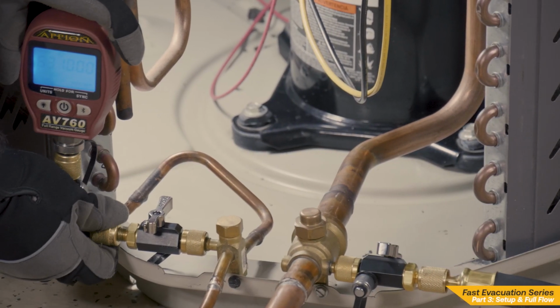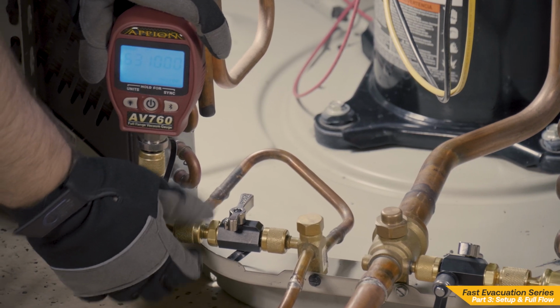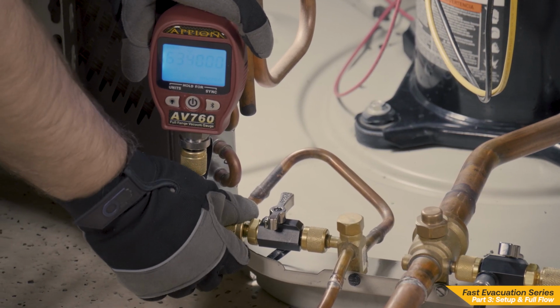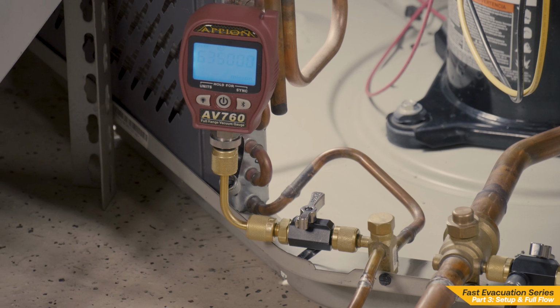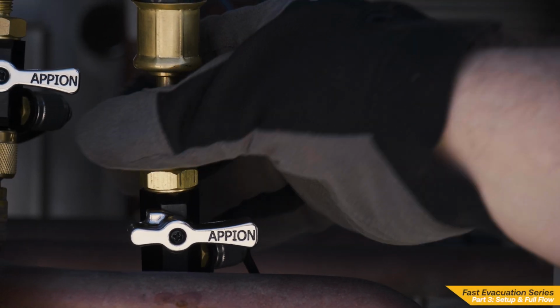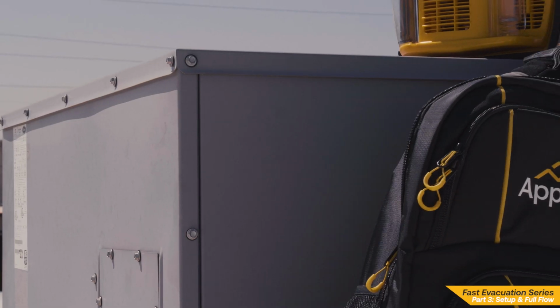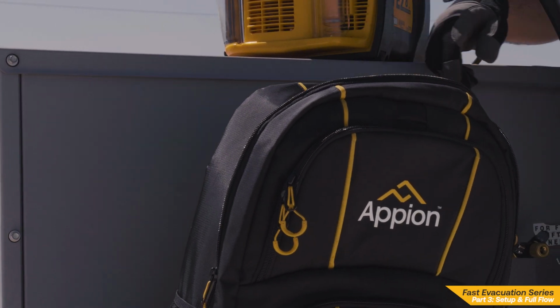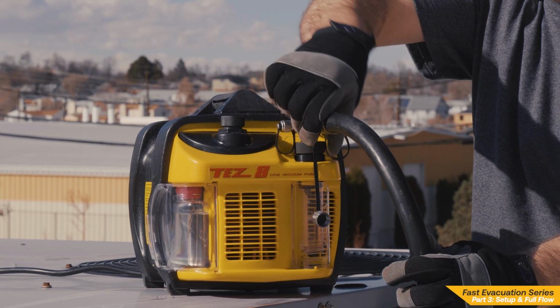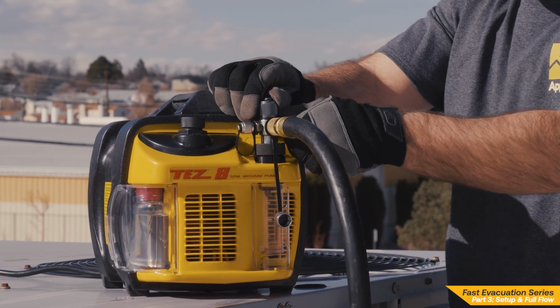If you insist on using a single hose setup, always attach your vacuum gauge to the opposite side of the system to ensure an accurate micron level reading. With your full flow setup ready to go, naturally you will want to begin the evacuation. In the next video, we will review how to diagnose a successful evacuation.